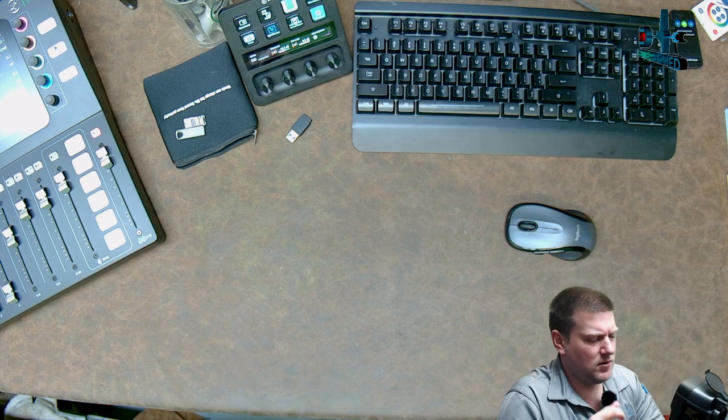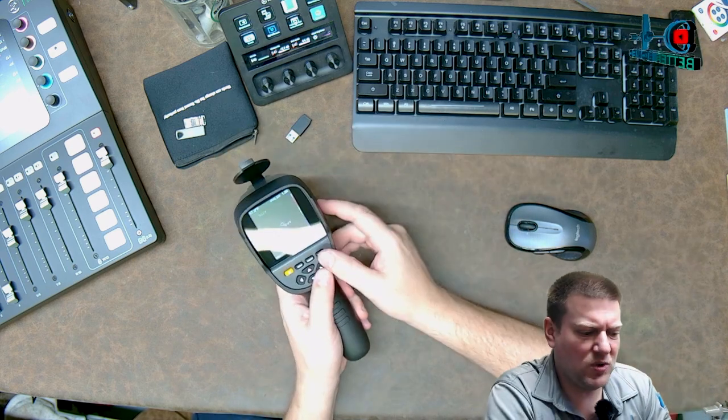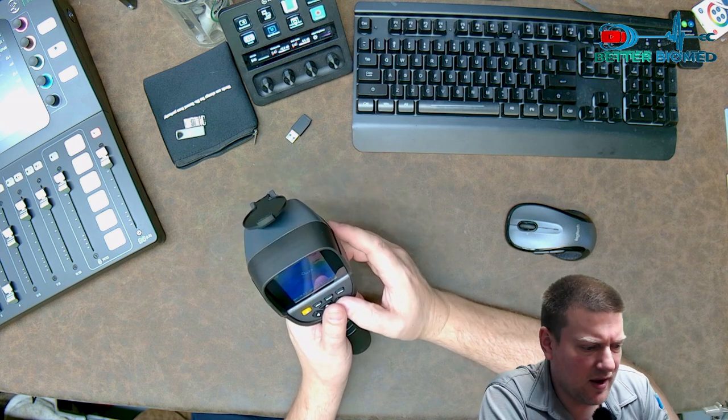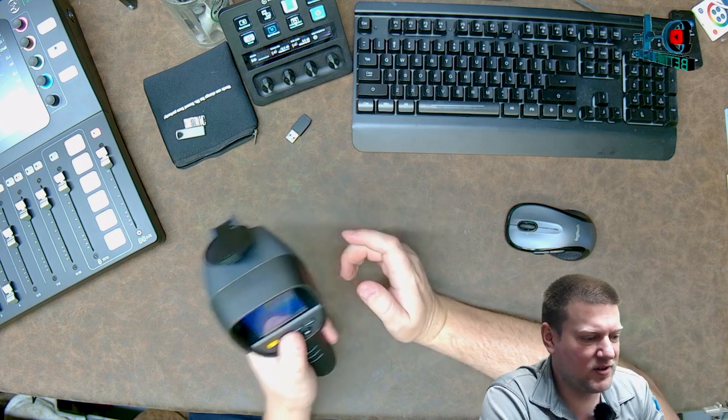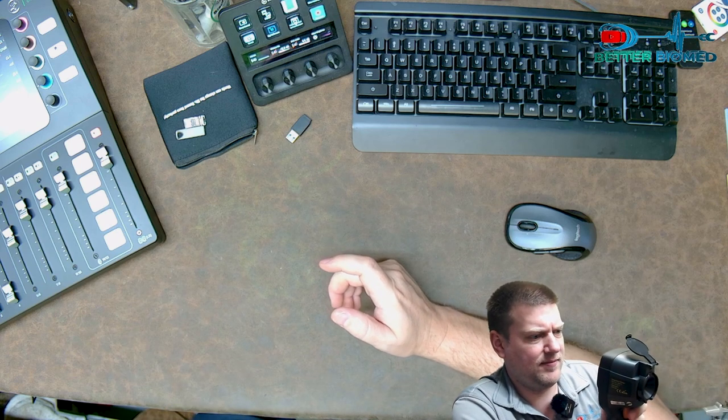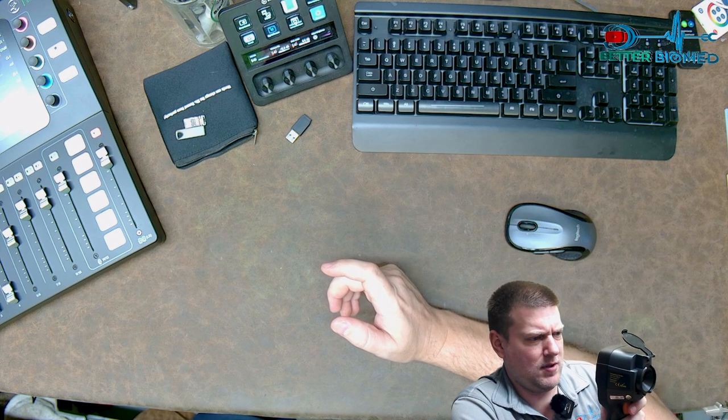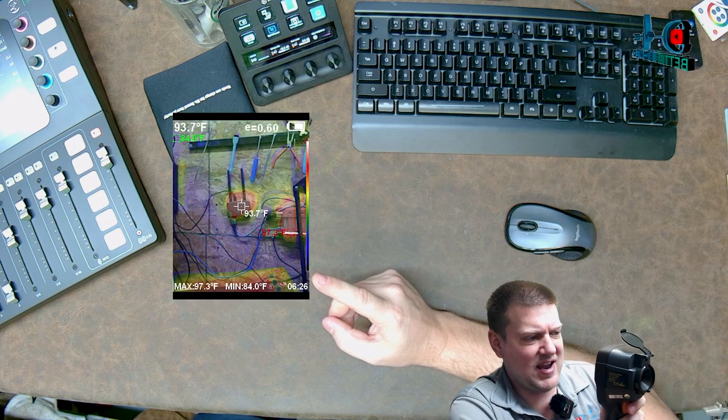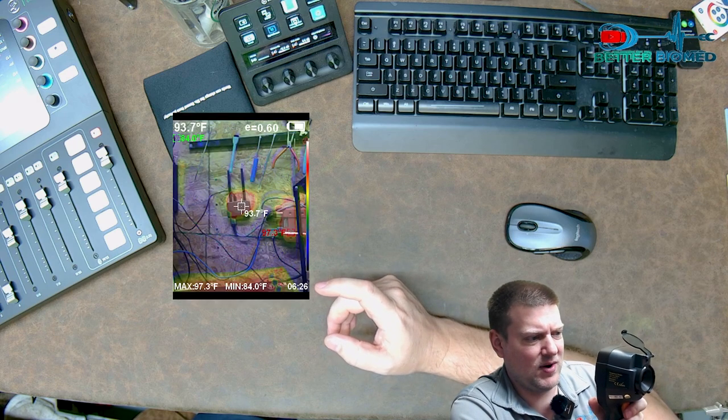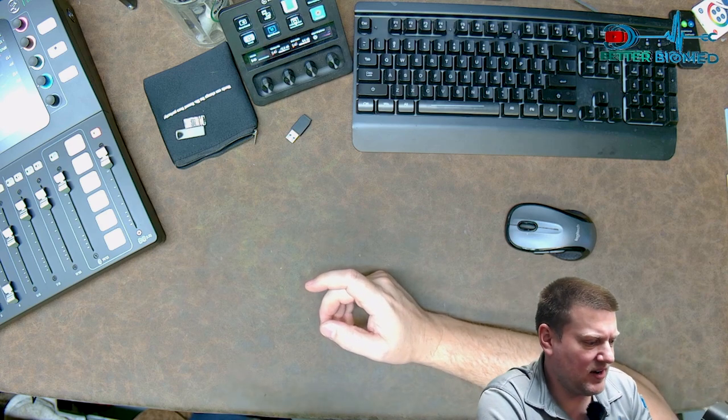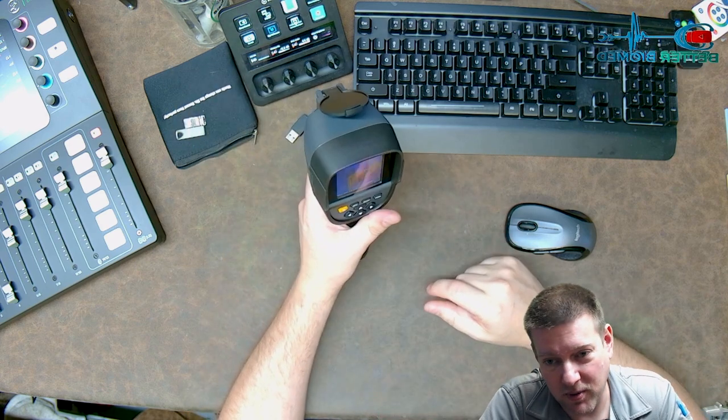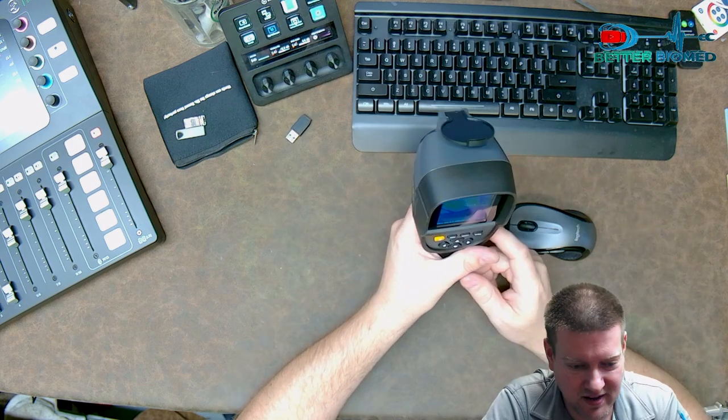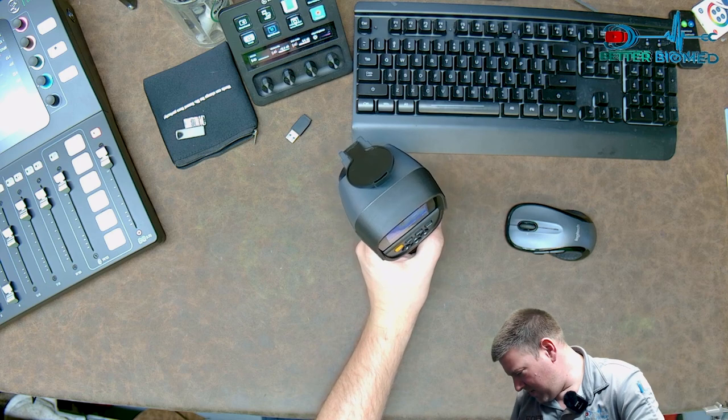And one of the cool things about these infrared guns is that in the infrared gun, it gives you a temperature of your target. So I can actually stand from across the room and I can look at an HVAC vent and I can scan it and I can tell you the temperature of it. Just the same, if there's a rack mounted of computers, I can stand back just like this and I can scan all the computers from one point and I can tell you what their temperatures are and I can save it by hitting a button. How cool is that? Let's see. How does my computer look? It says it's 84 degrees. Now the base of this computer is actually nice and cool. I dig it. That module over there on my wall is running at 93 degrees. That's crazy. 93 degrees. And I don't have to put a thermocouple on it to test that. I can run an infrared gun and I can tell you that.